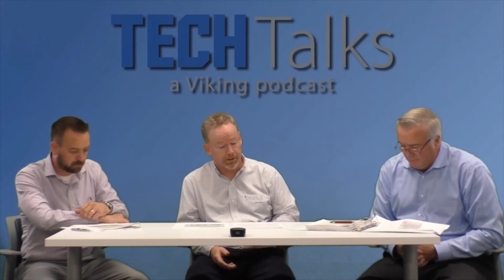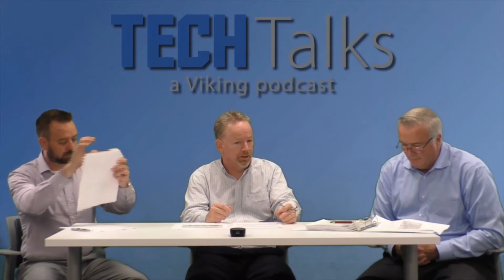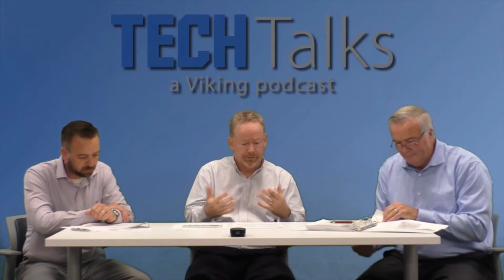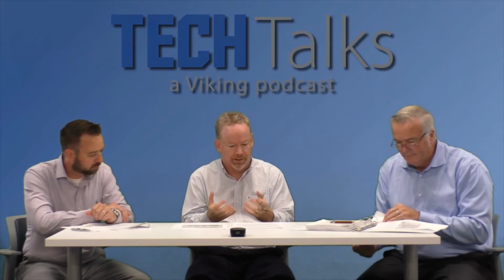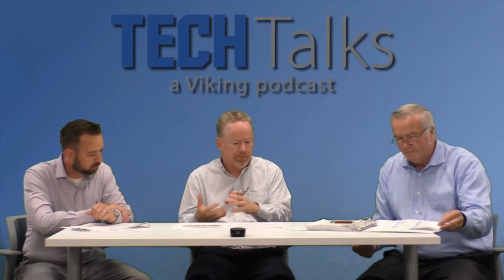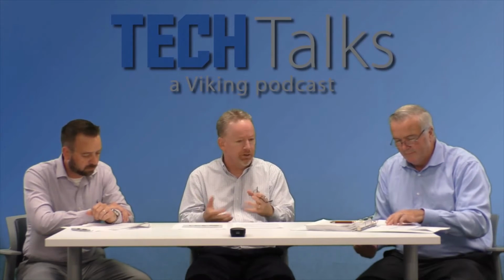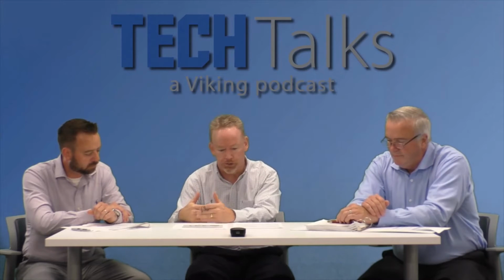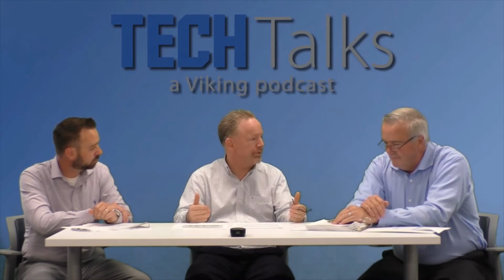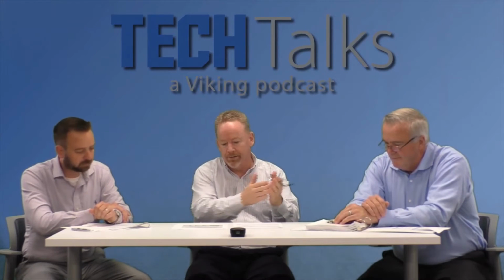Okay. All righty. So each one of you have mentioned this shape factor. So let's move along into that one. That the kind of the history of the shape factor, or the reason that we have one, and in some ways, NFPA 13 and FM 8-9 have been similar in their shaping and the way we shape a hydraulically most remote area, whether it's an occupancy hazard classification approach or it's the storage approach. It's a rectangular shape with the longer edge of the rectangle 1.2 times the square root of the area, and you're including all of the sprinklers there.